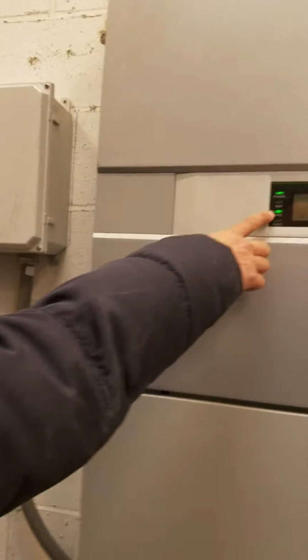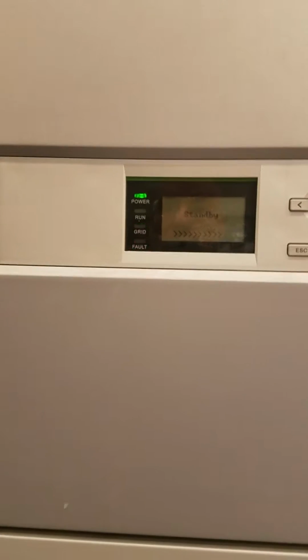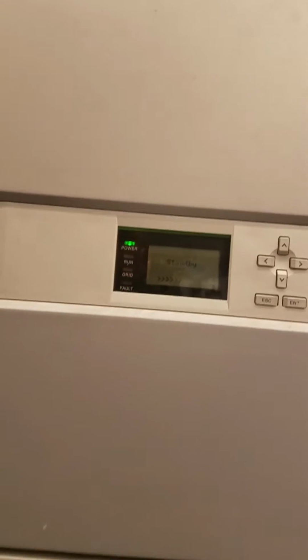But here, what you basically do is you shut it off like that, and wait for 5 minutes, and if the fault is still there after the 5 minutes, I'll come over and plug it into the laptop and see what's going on. Usually, to be honest, they usually give the first trouble in the first 6 months, from the delivery or whatever, they might have gotten a bang or something. But if after 6 months, you've never had any trouble, it'll last like 10 years.